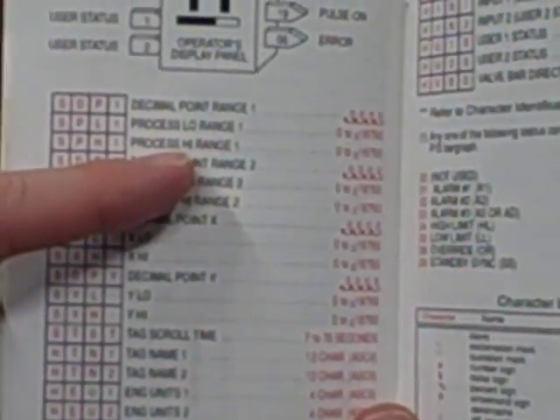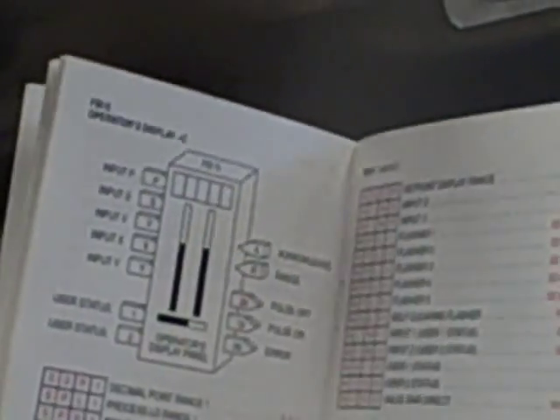In our case, we are interested in modifying function block number 15 to set our process low and high range values. These are the lower range and upper range values, respectively. This will show the display how to scale the indication according to whatever calibration you have in your temp transmitter.